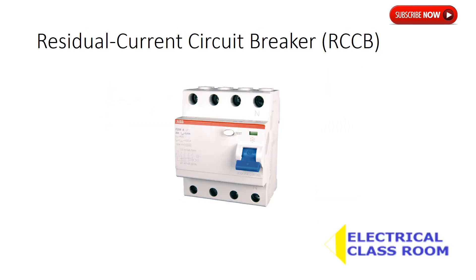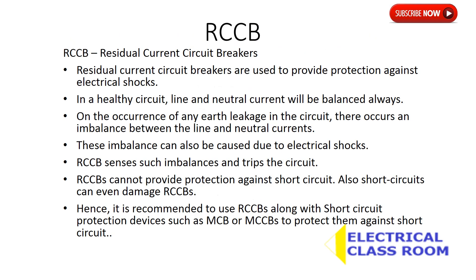Residual Current Circuit Breakers are used to provide protection against electrical shocks. In a healthy circuit, line and neutral current will be balanced always. On the occurrence of any earth leakage in the circuit, there occurs an imbalance between the line and neutral currents. This imbalance can also be caused due to electrical shocks. Residual Current Circuit Breakers sense such imbalances and trip the circuit.